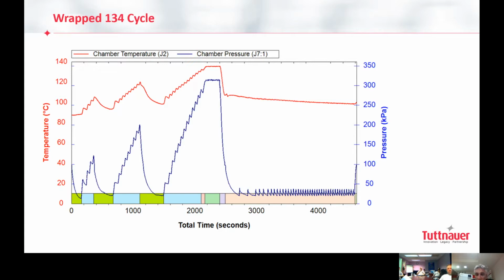Thank you. Okay. Now, theoretically, we said we have to remove more than 99% of air from the chamber. Okay, I will move from here to the... theoretically, we said that we have to remove 99%. So it was very easy for us if I take a very aggressive, strong vacuum pump and just suck all air from the chamber. So once we close the door, at this moment we have 100% of air inside the chamber, correct? I have to get free of 99. So I can take a pump and just suck 99% out.